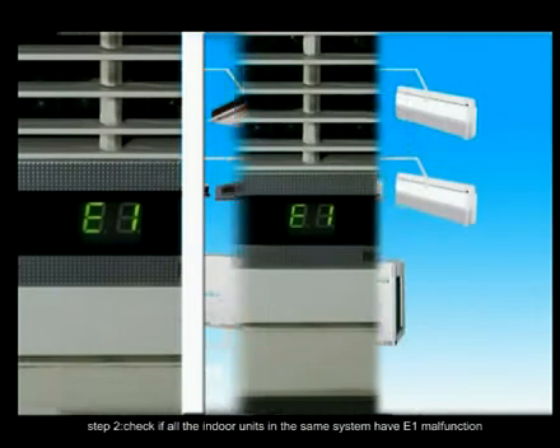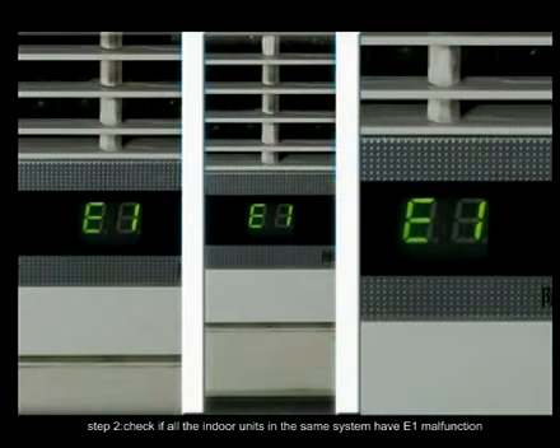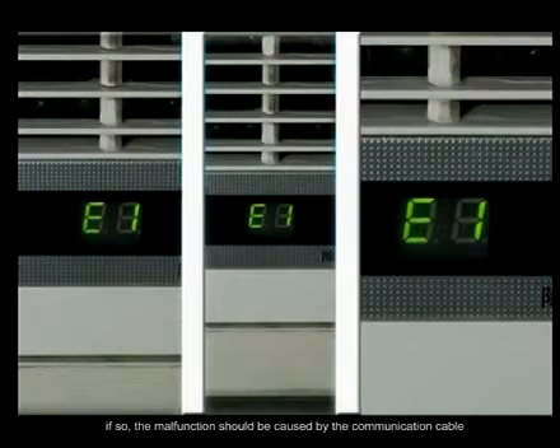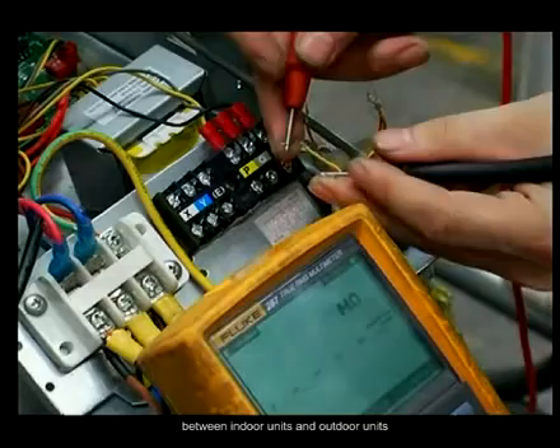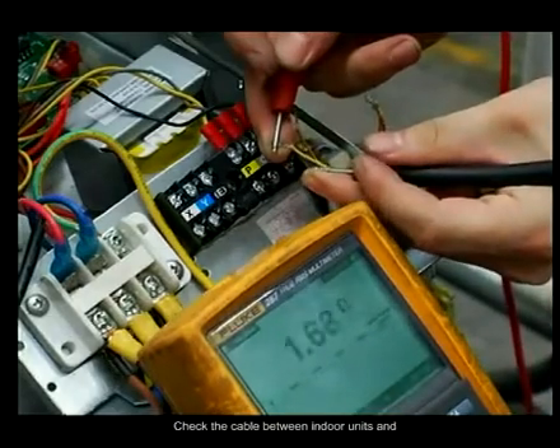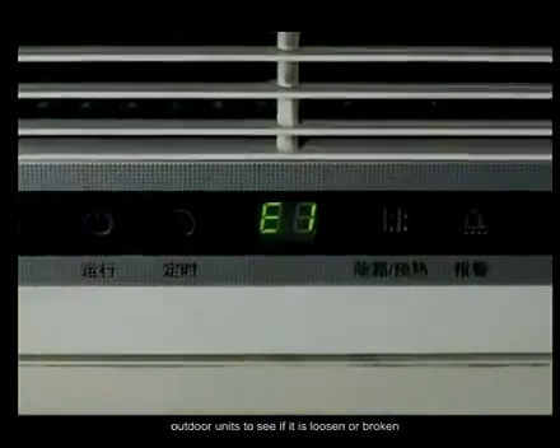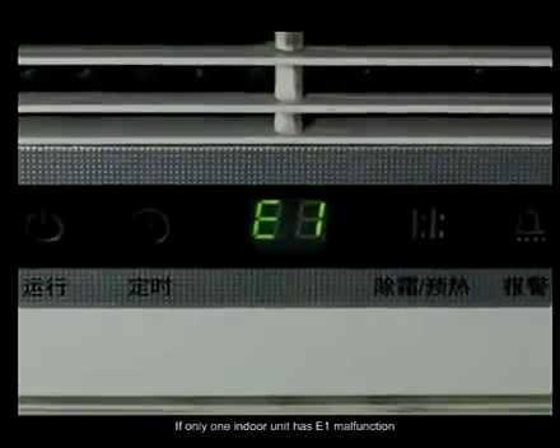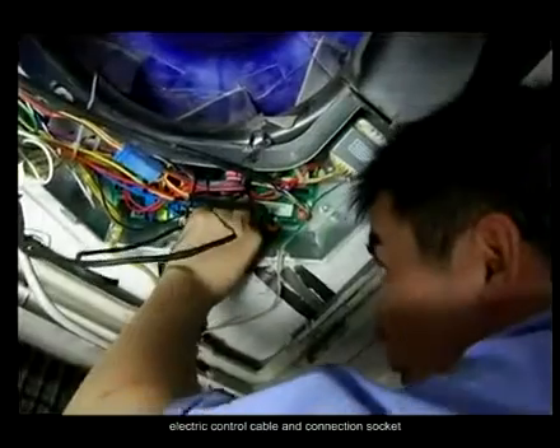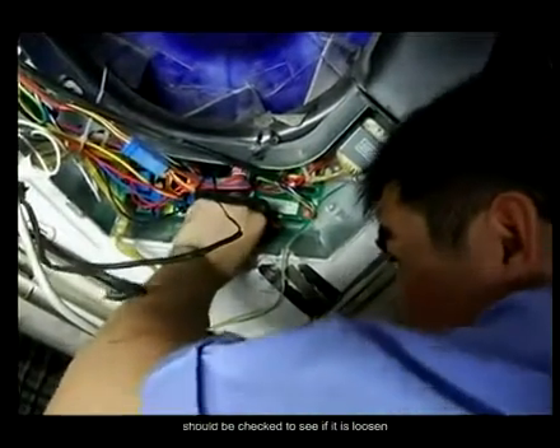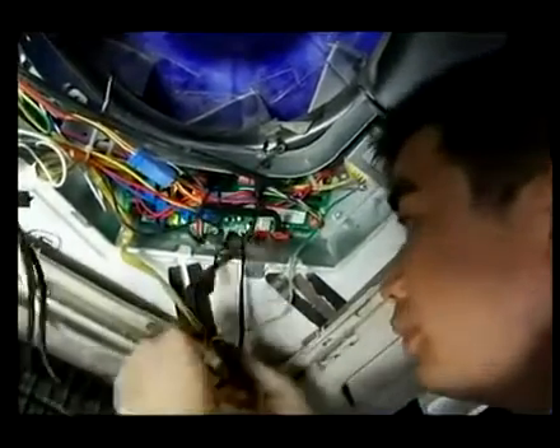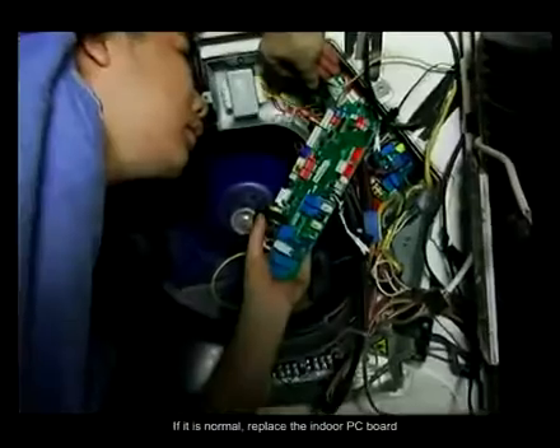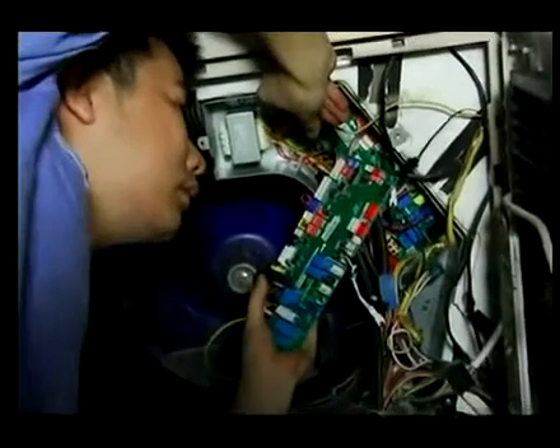Step 2. Check if all the indoor units in the same system have E1 malfunction. If so, the malfunction should be caused by the communication cable between indoor units and outdoor units. Check the cable between indoor units and outdoor units to see if it is loosened or broken. If only one indoor unit has E1 malfunction, the electric control cable and connection socket should be checked to see if it is loosened. If it is normal, replace the indoor PC board.